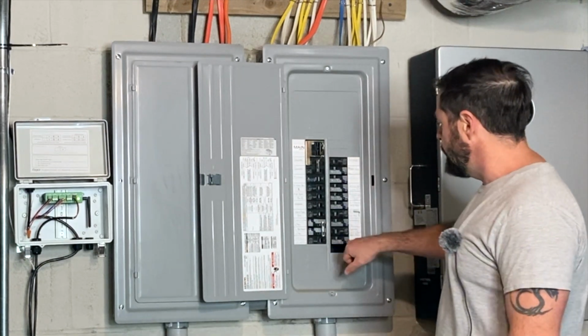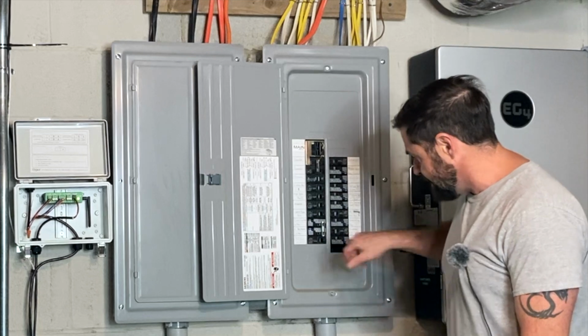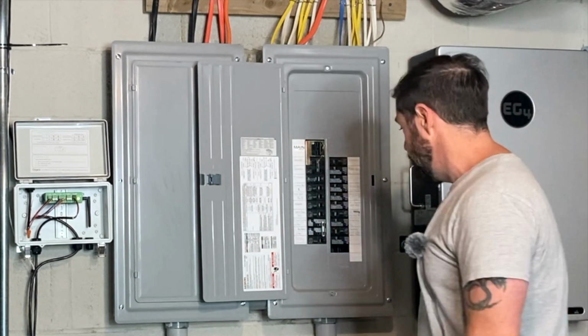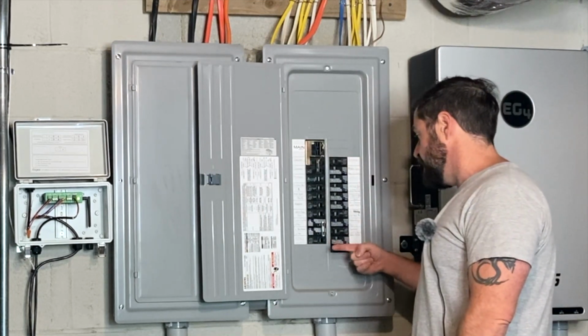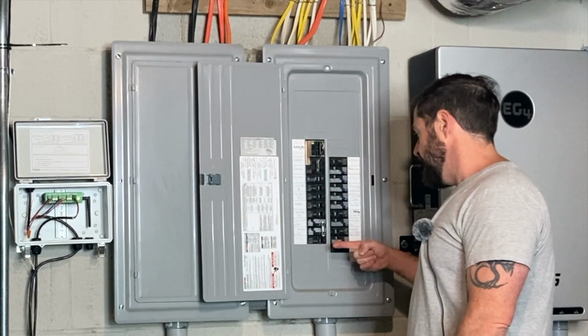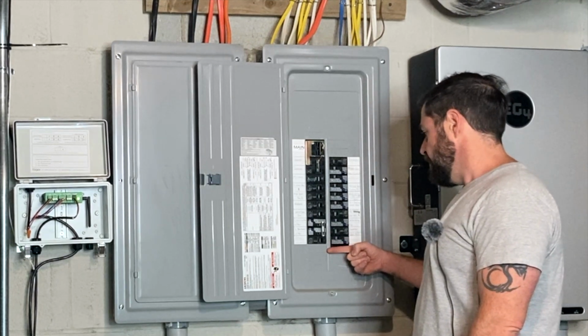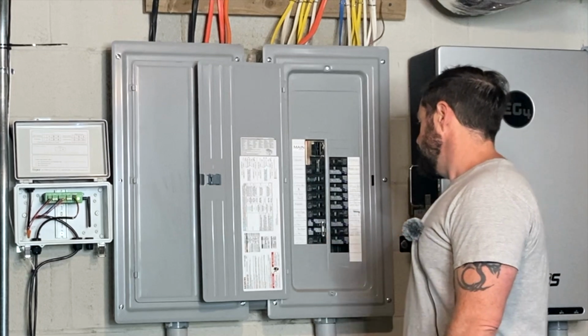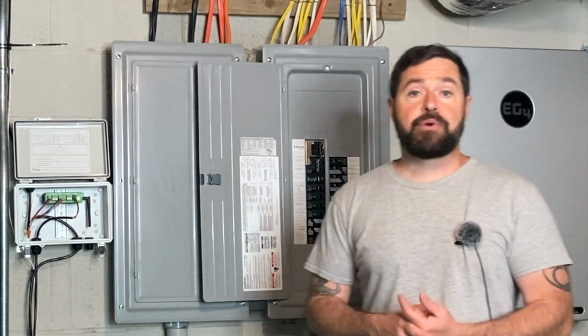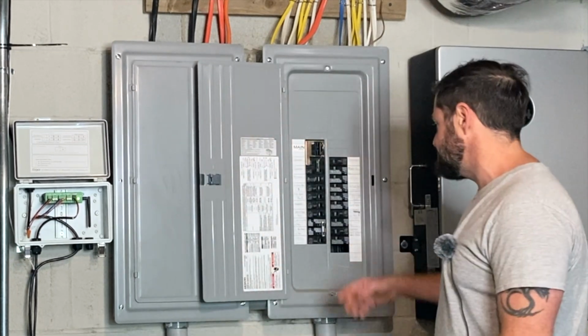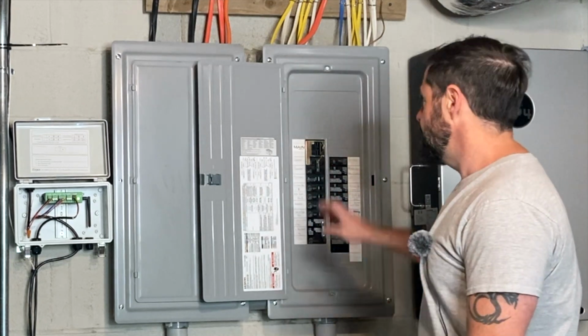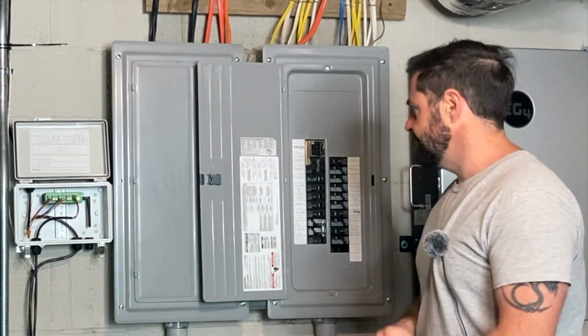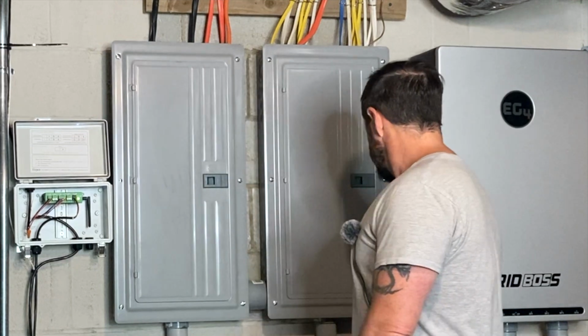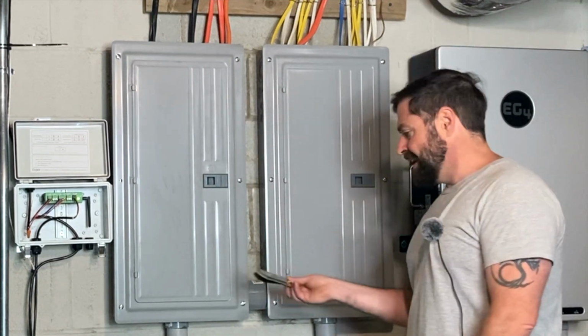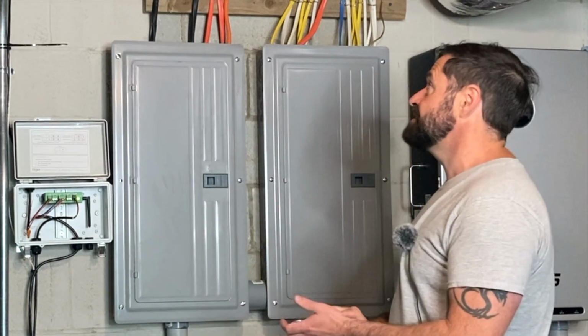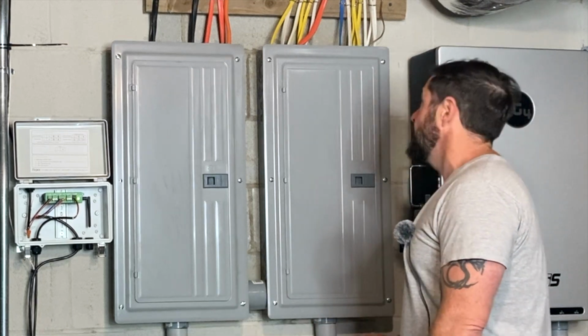Here's a hole in the dead front cover where somebody could stick their finger in there and get electrocuted. We need to plug that with either a spare circuit breaker or a little breaker cover. I prefer spare circuit breakers because those little plastic covers tend to fall out when you take the dead front covers off and on. I got to get all my covers on my LBs -- a bunch of those are open at the moment.